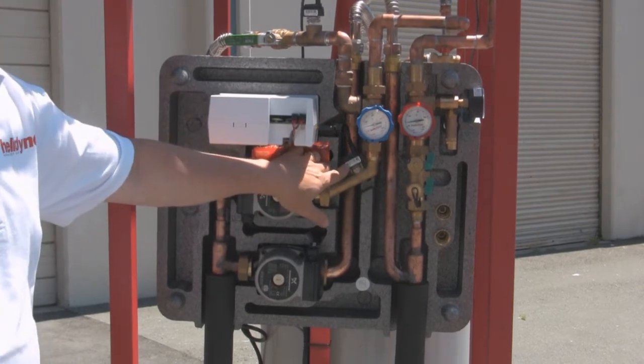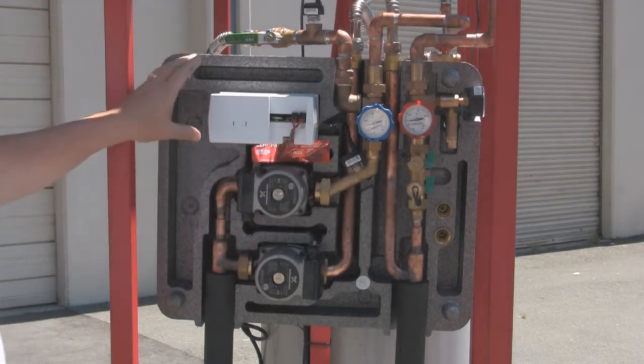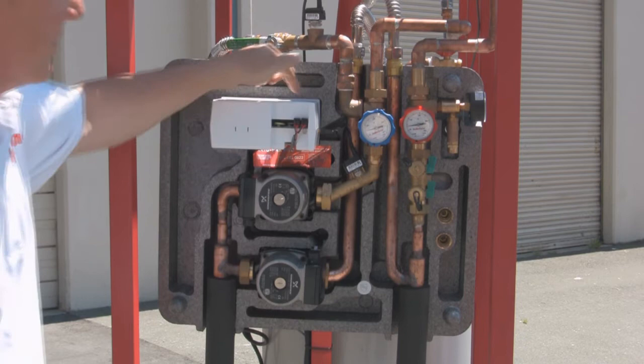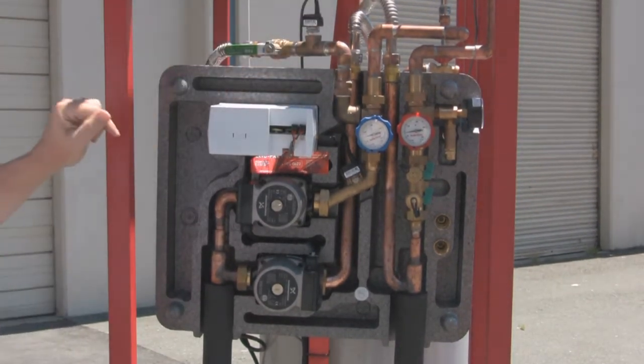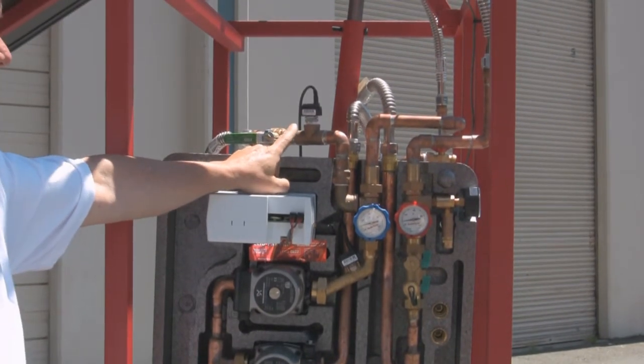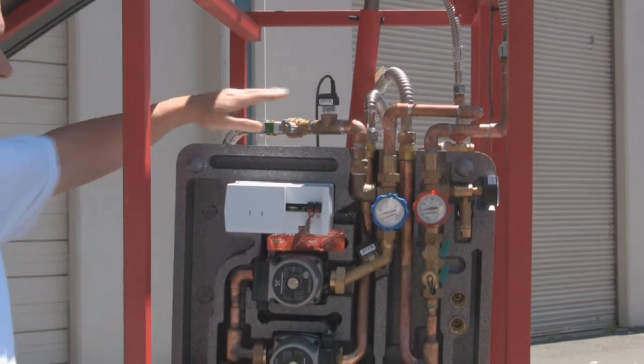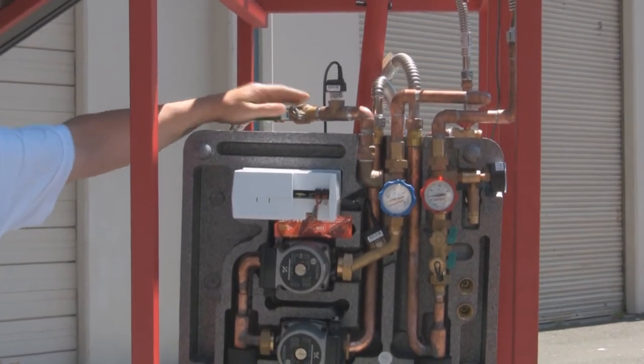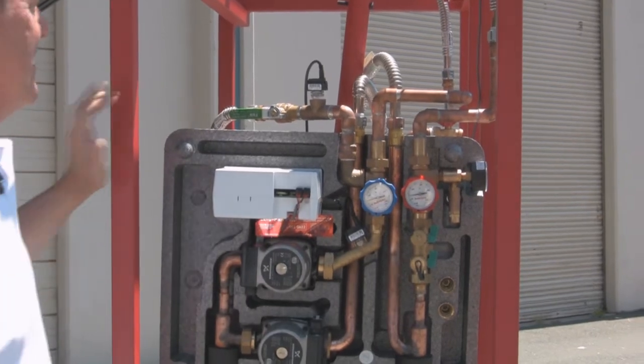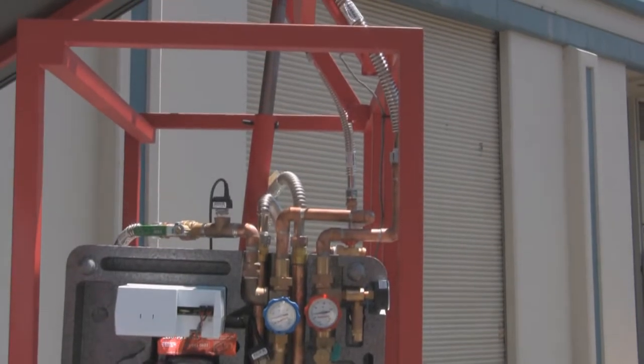This is a Grundfos digital sensor that senses both flow and temperature. This is the Heliodyne controller, which has a built-in web server — this one is a wireless model. And this is a pressure sensor, also made by Grundfos, which senses both pressure and temperature. There's also an isolation valve to allow us to isolate the expansion tank located behind the H-PAC, and flexible stainless steel tubes that connect the system together.